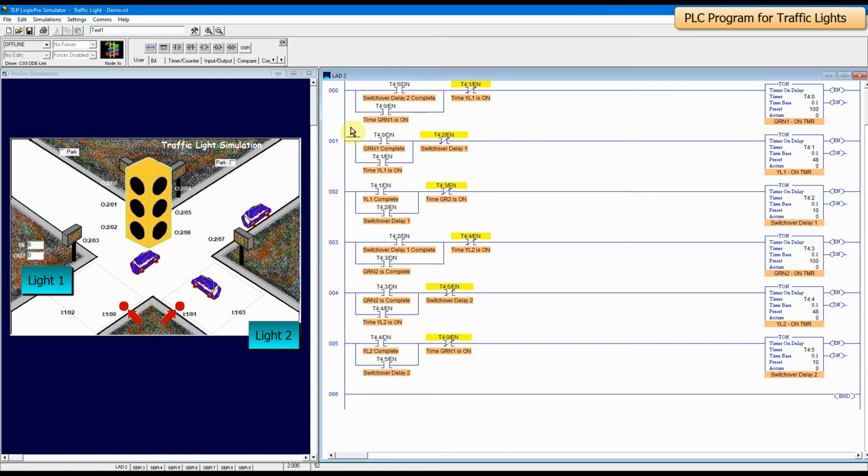We're sealing in the event, or the enable for each timer, to ensure that the next event starts before I allow the first column tasks. I seal in this task until the next task has started. That way I can actually interrupt the process without losing the previous task, which is another point. So I'm just kind of planning ahead here a little bit, thinking, okay, I might actually need that kind of functionality in the future, so I'm going to program it in. Doesn't hurt to have that seal in there.